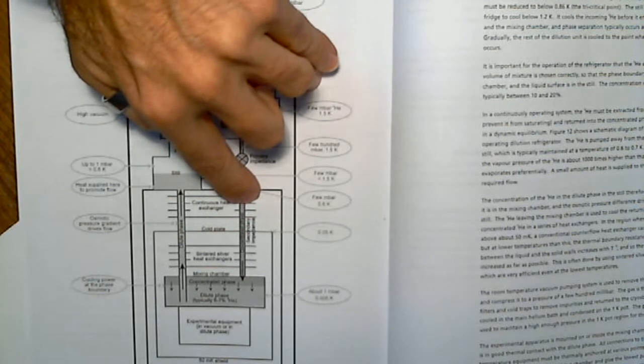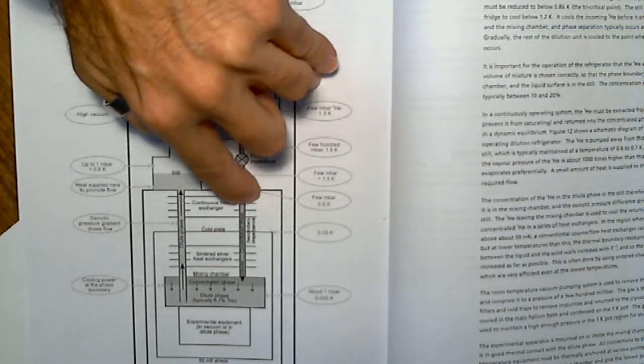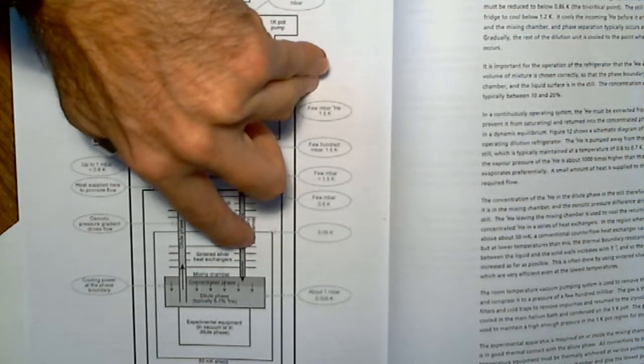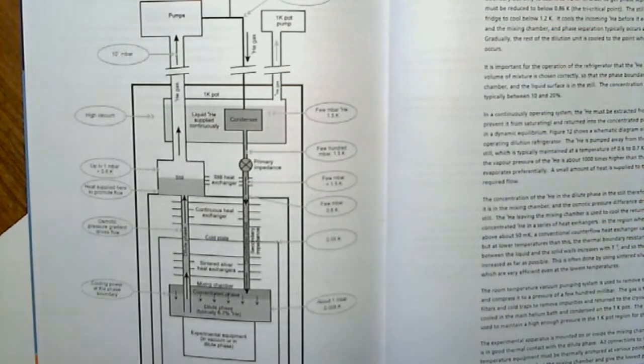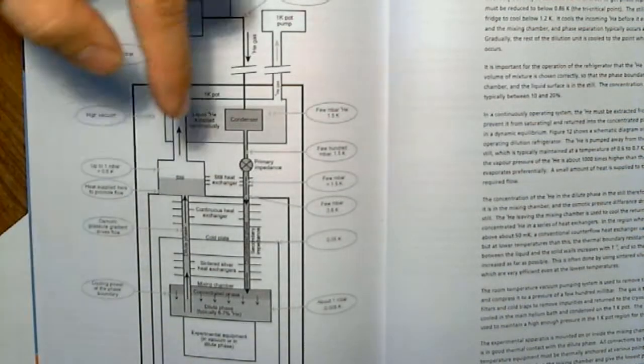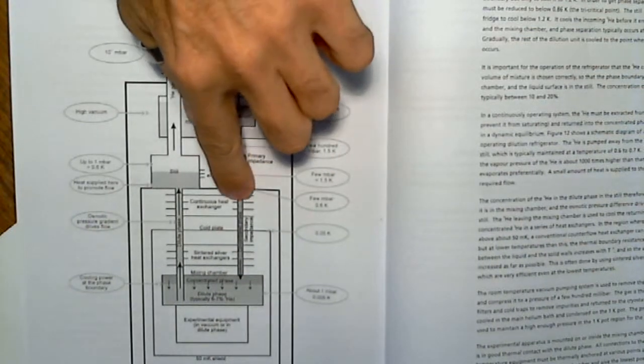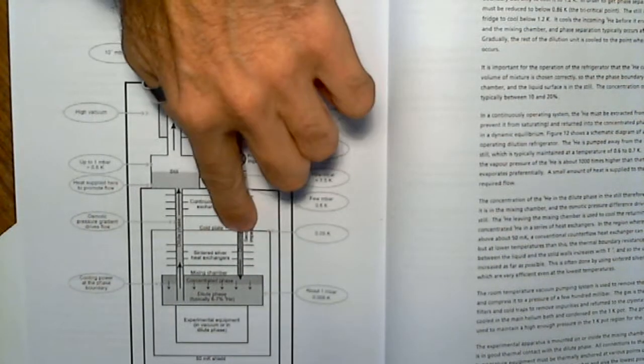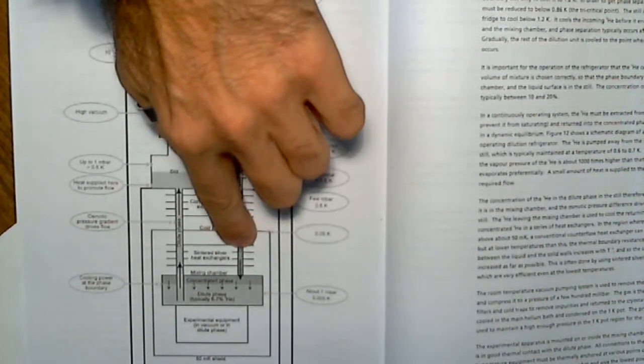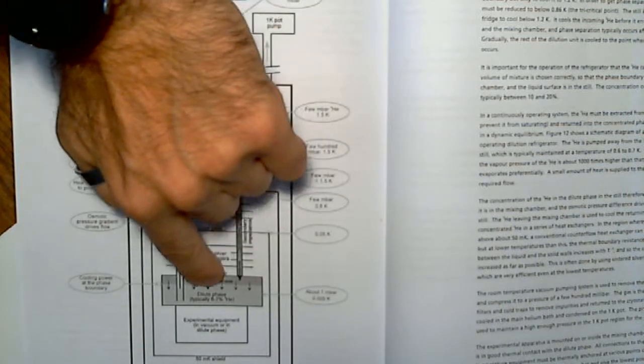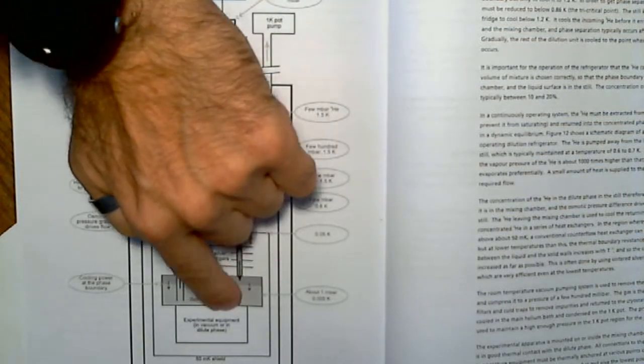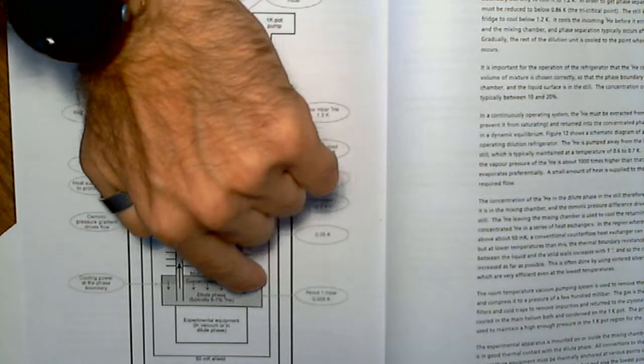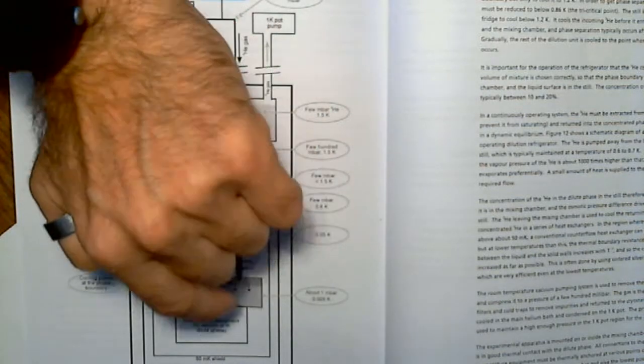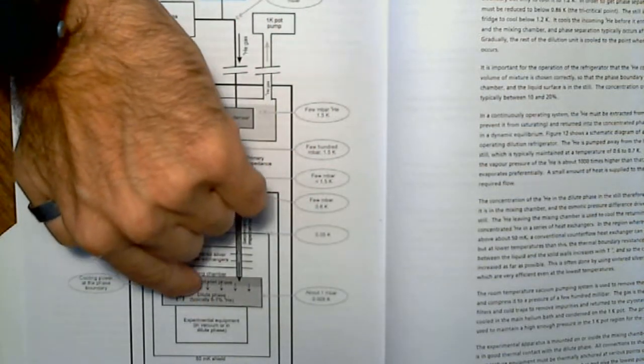You have a continuous heat exchanger, and then a step heat exchanger. It's really a tube with some sinter material inside. You flow the mixture through this heat exchanger, first down to the mixing chamber. This part here is the mixing chamber. As I explained yesterday, you have these two phases from helium-3 and helium-4, and you pump out from the other side.